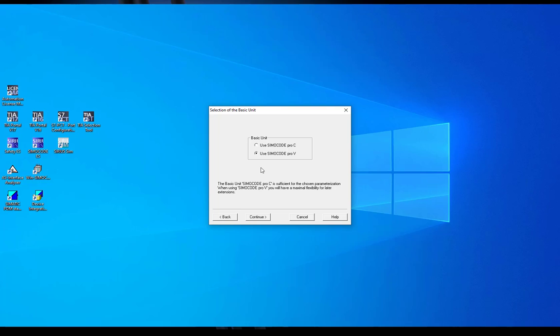Further the 3UF5 compatibility mode was selected at the beginning of the conversion. So SIMOCODE pro V basic unit is no option for that requirement. Let's see if Siemens brings another hotfix to fix that.